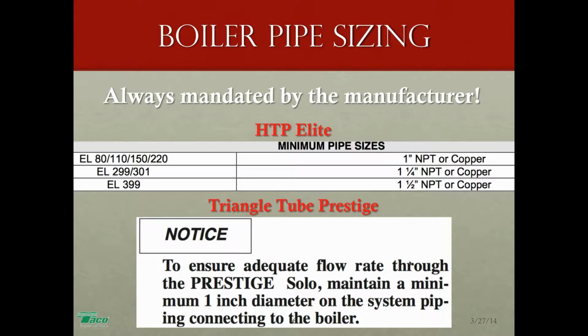Triangle Tube Prestige, from their installation manual: to ensure adequate flow rate through the Prestige Solo, maintain a minimum 1 inch diameter on system piping connecting to the boiler. That's to maintain a flow. Now, these boilers are very flow dependent in their operation. In order to scrub the heat exchanger, in order to keep those things from bopping off on high limit all the time, you have to have a very specific flow rate through that heat exchanger. They will tell you what size pipe that should be.